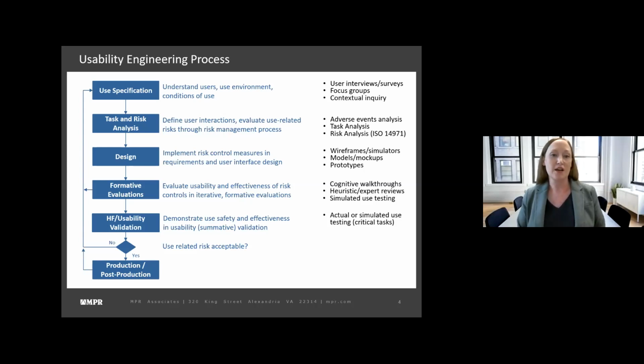Throughout the design process, the design is evaluated through iterative formative evaluations that we can use to evaluate usability and the effectiveness of risk controls throughout development. At the end of the design and formative evaluation process, when we have a final production equivalent design, that's where the human factors validation comes in, which is sometimes also referred to as the summative validation, where really the focus is to demonstrate use safety and effectiveness on the final user interface design. That will allow us to conclude whether the use-related risk is acceptable. If it is, then we're ready for launch.